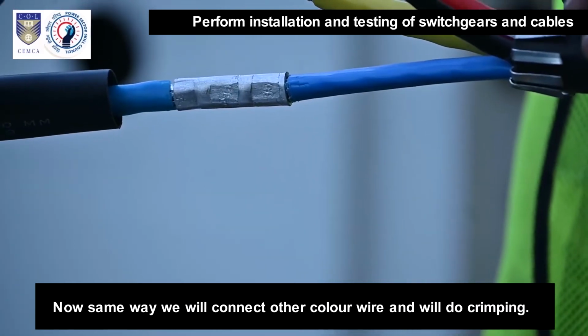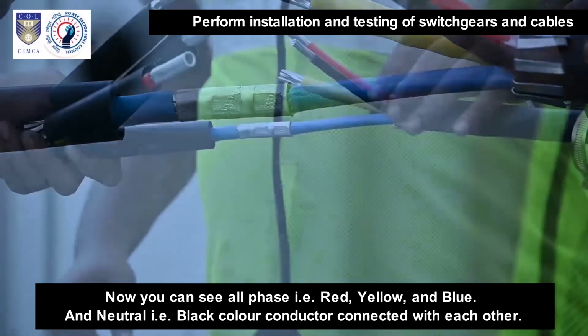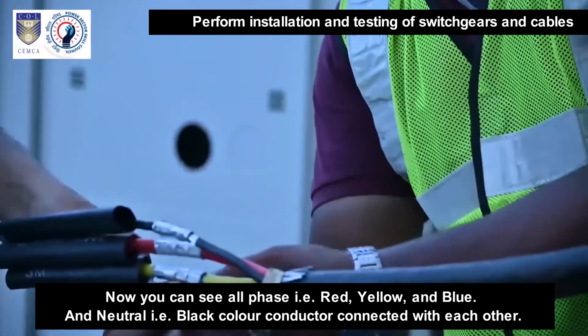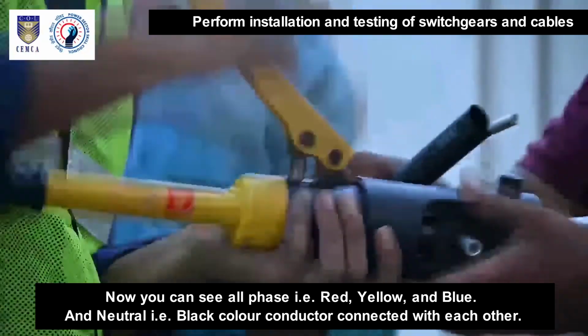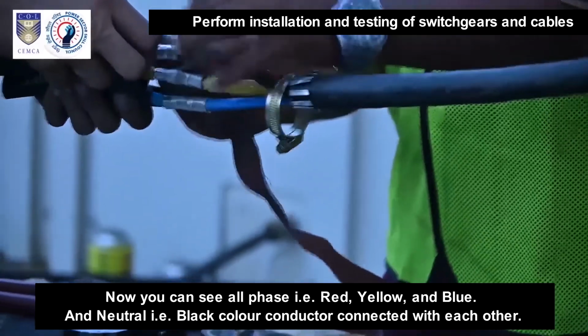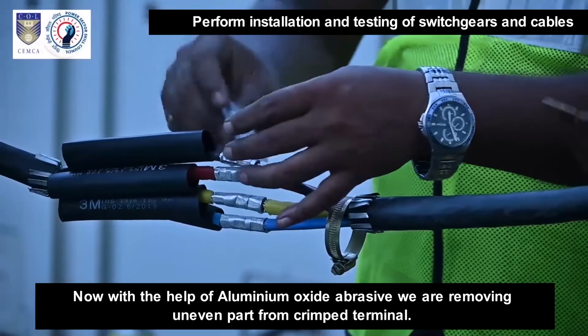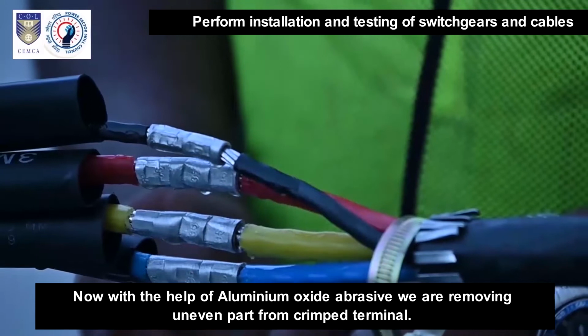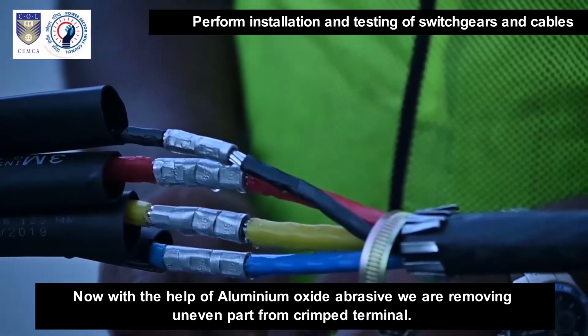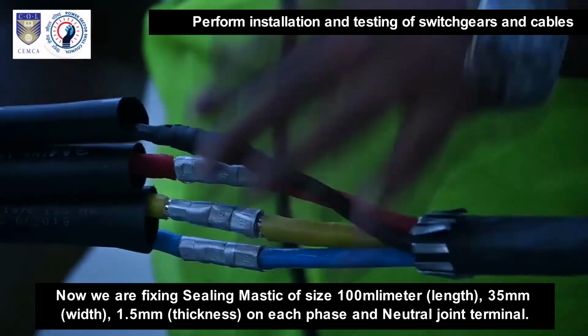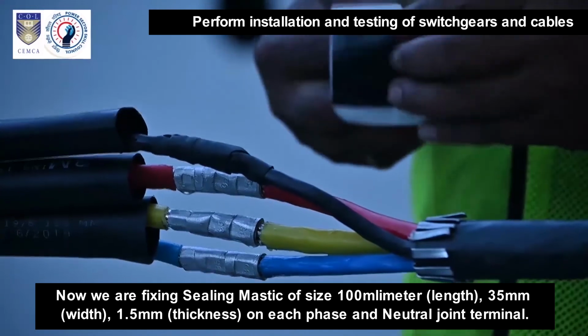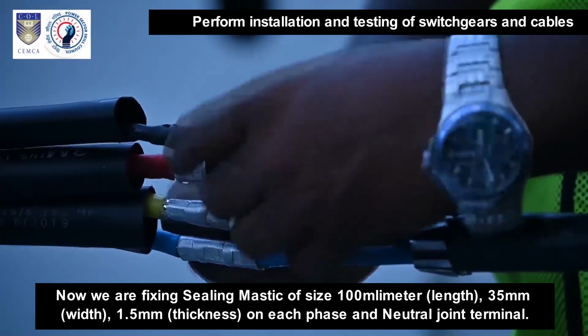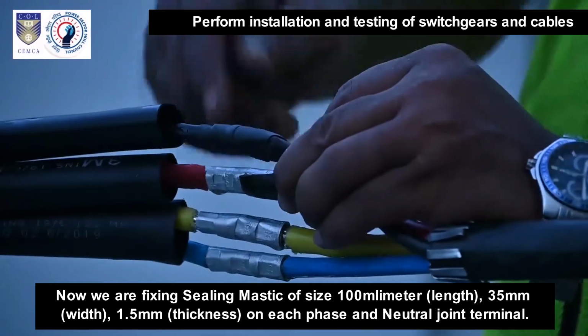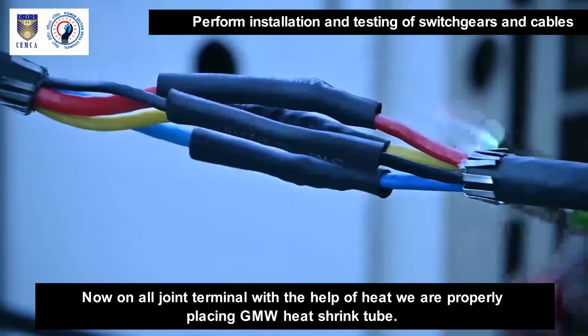Now in the same way we will connect the other color wires and do crimping. Now you can see all phases, that is red, yellow and blue, and neutral, that is black color conductor, connected with each other. Now with the help of aluminium oxide abrasive, we are removing uneven parts from the crimped terminal. Now with the help of cleaning solvent, we are cleaning all the terminals properly. Now we are fixing sealing mastic of size 100 mm length, 35 mm width, 1.5 mm thickness on each phase and neutral joint terminal. Now on all joint terminals, with the help of heat, we are properly placing GMW heat shrink tube.